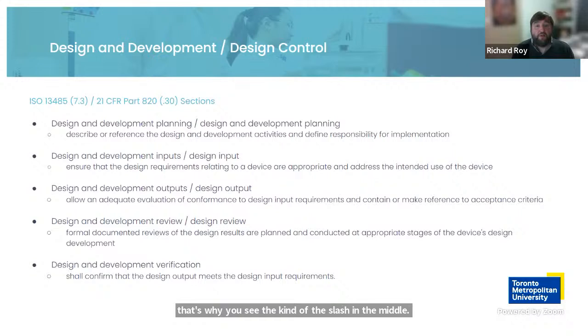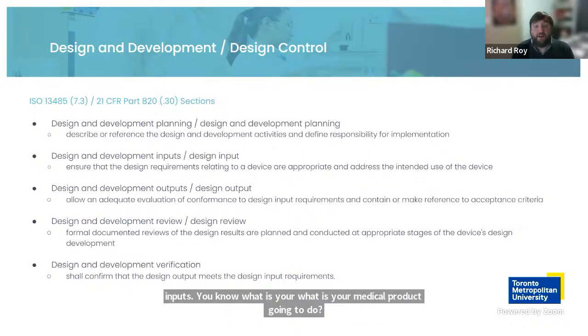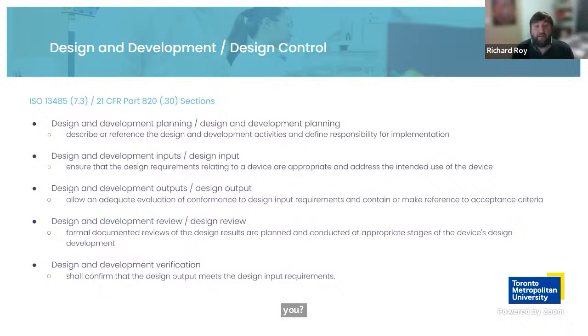But it's important, as you go through, you have your design and development planning, where you're developing a product, defining responsibilities, and defining your plan on how you're going to get to that end goal. You're establishing your design inputs. What is your medical product going to do? What is its intended use? Design outputs look at what that evaluation is going to look like to make sure it's doing what you need it to do, by establishing things like acceptance criteria. The design review process is critical to have during the stages of your product development. There are going to be iterations, there are going to be failures, and you continue those reviews and build off of that to make an effective product.